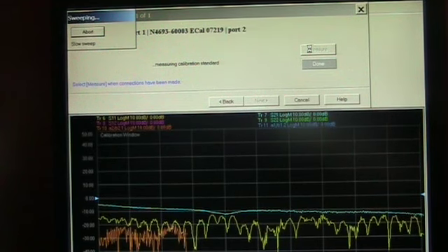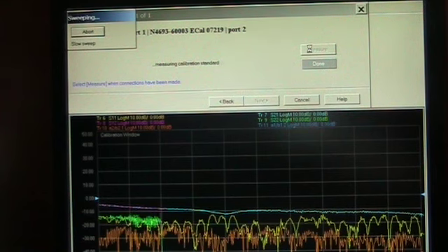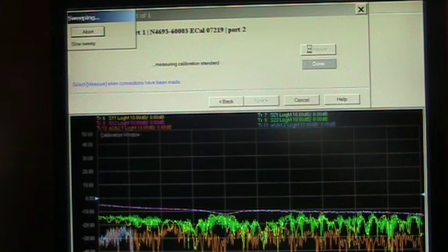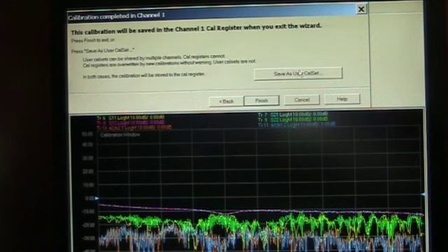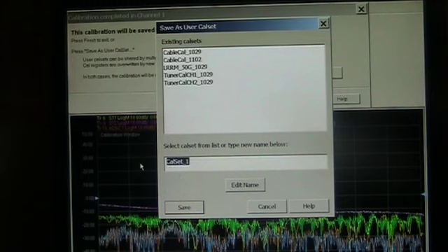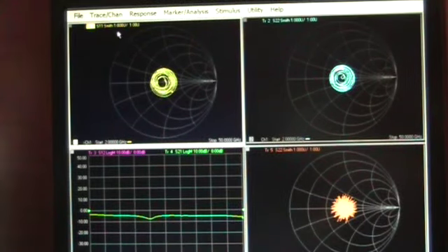Okay, the first channel is nearly done calibrating, so we'll go ahead and finish this up. And although this doesn't get referenced anywhere other than for verifying we got everything right, I do go ahead and save the name of this. We'll go ahead and save it and call it Tuner Cal CH1 and give it the date, because that's calibration pertaining to the first channel.